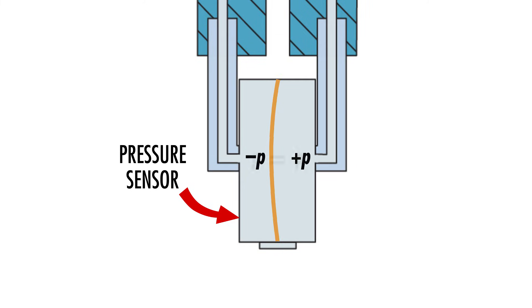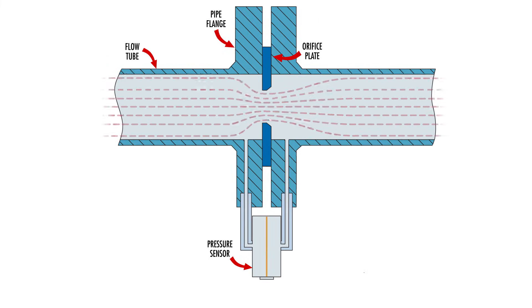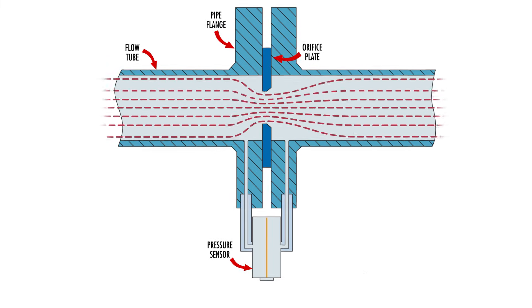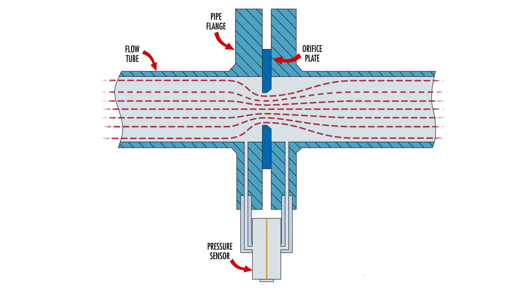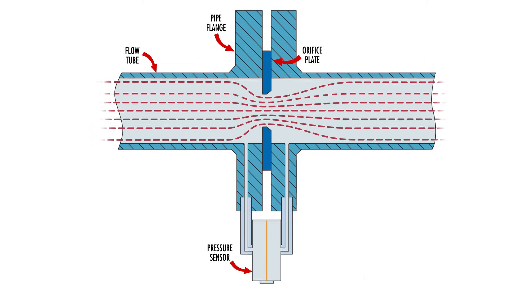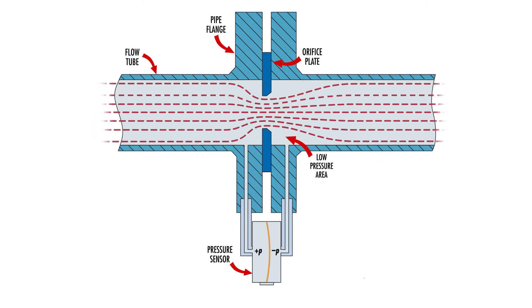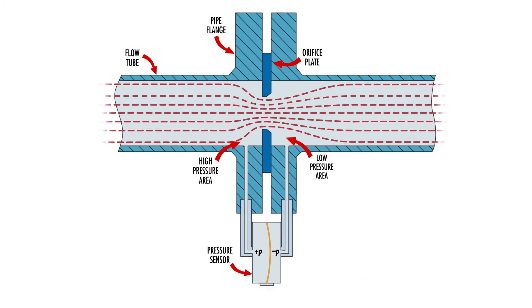When there is no flow, the pressure before and after the restriction is the same. Here's where Bernoulli's Principle comes into play. When the fluid begins to flow, the velocity near the restriction increases significantly due to the decreased cross-section at the orifice plate, causing the static pressure on the downstream side of the pressure sensor to decrease, while the upstream pressure increases.